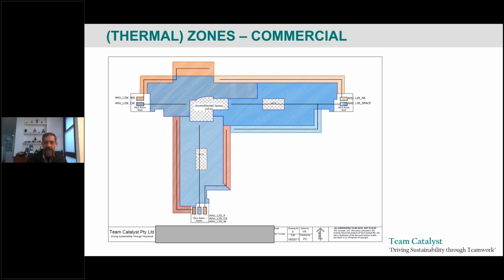The difference between these perimeter zones—the zones near the edge—and the center is that the edge zones interact with climate: the sun falls on the external wall and window, and temperature, wind speed, and rainfall all affect the external walls. The internal zone doesn't really have any of those interactions. If the air conditioning engineer chooses to put fresh air in, that's the only interaction that internal zone has with the outside, so there's a separate air handler conditioning it.